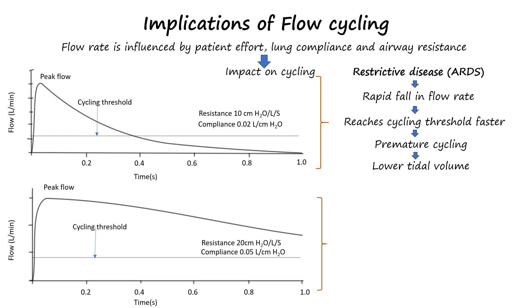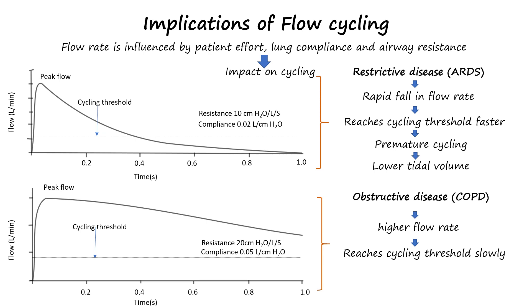In contrast, the patient with emphysematous lung disease may have very high lung compliance with greater flow using the same ventilator settings. As a result, the flow won't reach the prescribed threshold percentage, leading to prolonged breath or delayed cycling. It is therefore important to understand the lung conditions of the patient before setting the cycling threshold.